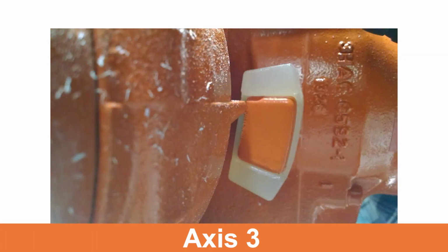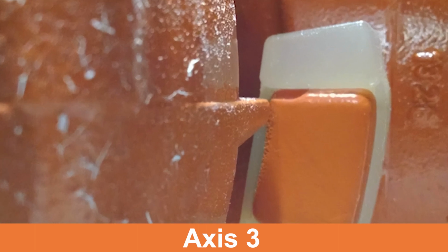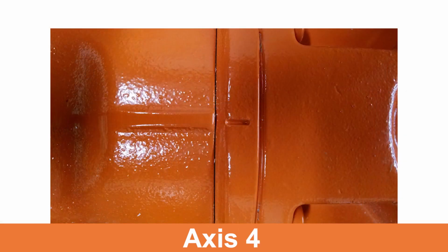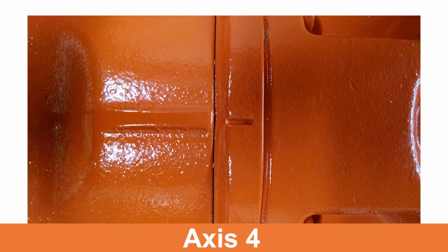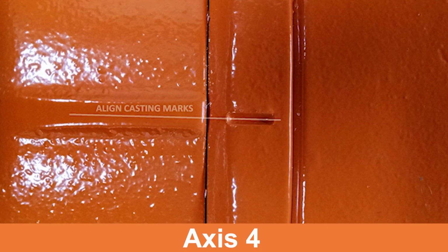The purpose of moving to this position prior to the SMB battery replacement is to verify that the witness marks are properly aligned, and since removal of the battery will cause revolution counters to be lost, it will be easier to update the revolution counters since all axes will already be at their calibration position.